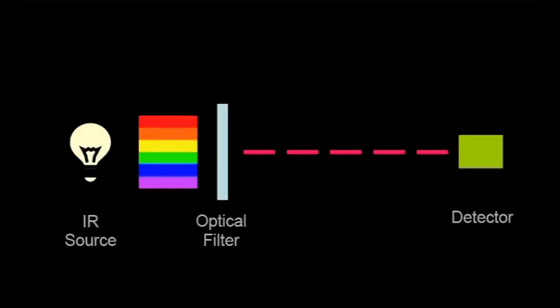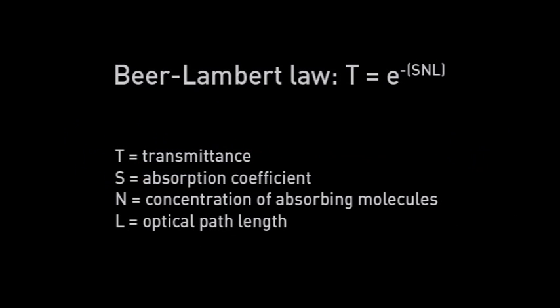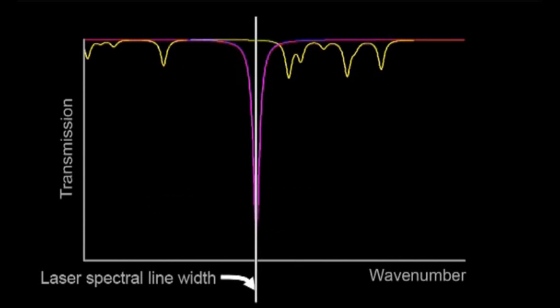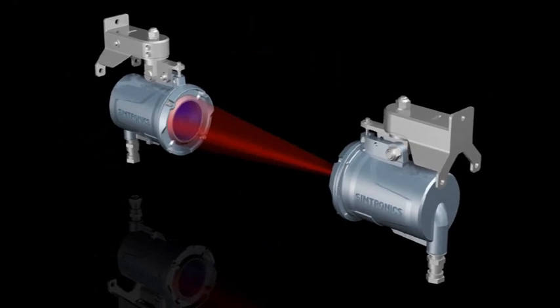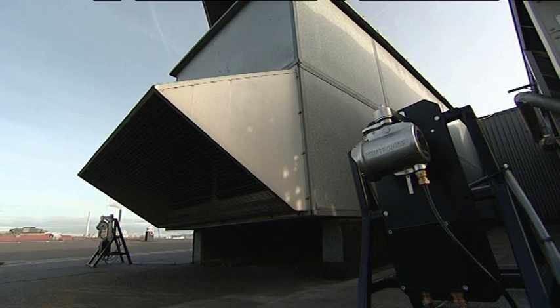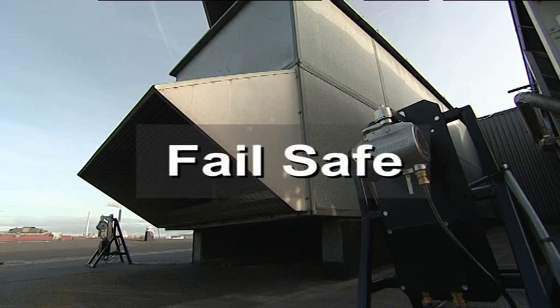The Simtronics concept for hydrogen sulfide detection is based on infrared light absorption, with the amount of light absorbed being related to the gas concentration by Beer-Lambert's law. By using a tunable laser diode, we can scan absorption lines with little cross-sensitivity to other gases. The new GD1 toxic open-path gas detector is designed to work safely in extreme environments.